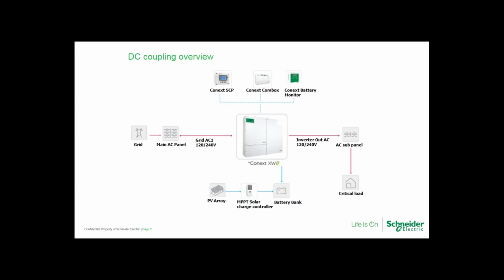Really, the only way to do that with the existing platform is to incorporate relays, which is possible to do. You can program the auxiliary port to close when you reach the bulk level, and that could connect to your additional charge controllers. So that's one way you can get around having a small battery bank. But as long as you're aware of that limitation, you won't get into a similar position where you're stuck having to scramble for a solution because the system wasn't designed properly in the first place.